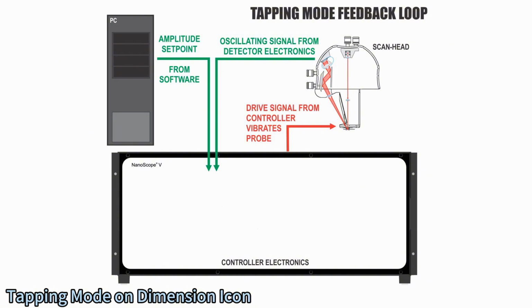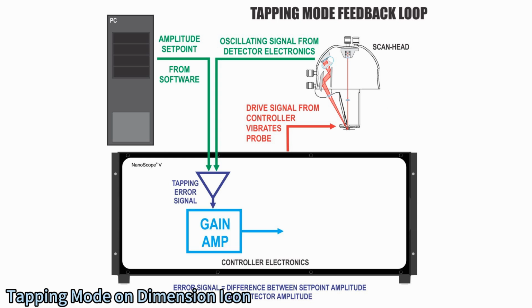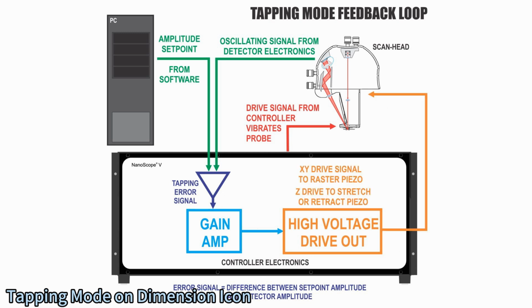The user enters a setpoint value through the software interface that represents the desired amount of resonance amplitude. The signal from the photodetector is compared to the setpoint value, and the resulting difference is known as the error signal. The error signal is fed into a gain amplification circuit, which influences the controller's response to the variation from the setpoint. The amplified values are then fed to the high-voltage control circuitry to send the required voltage values to the scanner that will force the piezo to retract or extend to maintain the setpoint value.